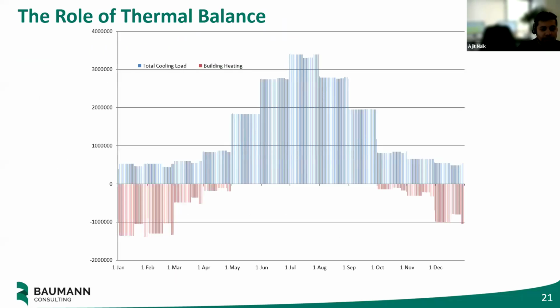I've talked a lot about the battery aspect, the storage, about how geothermal systems are fundamentally different because they let you store heat under the ground, like a squirrel storing nuts, and use it for the winter. This means it's important to have some balance. If you take a certain amount of heat out of the ground in winter, you better be recharging it somehow, otherwise the ground will eventually freeze. Conversely, if you keep putting in more heat than you take out, it will eventually overheat.